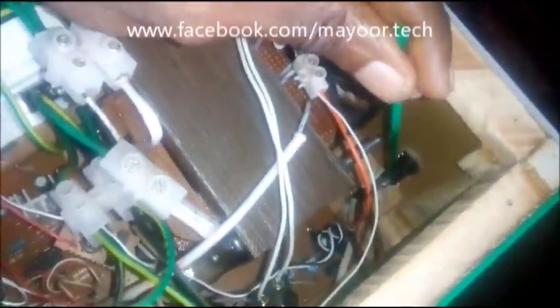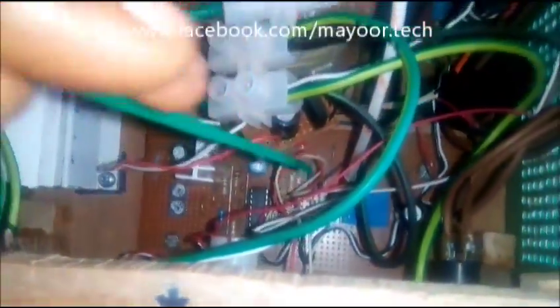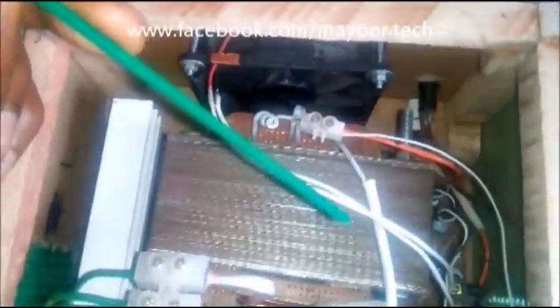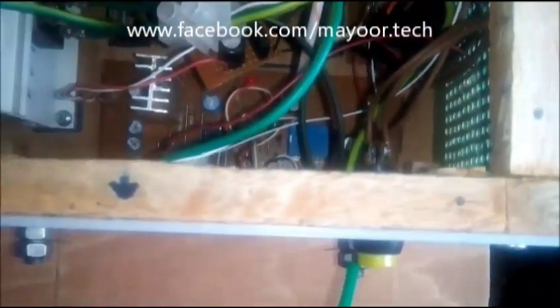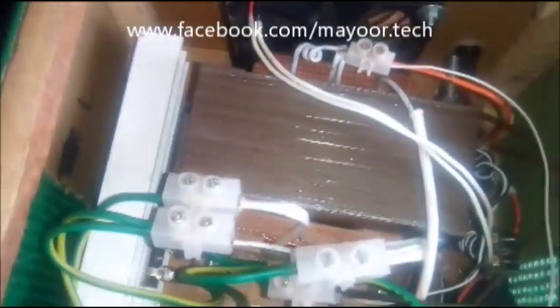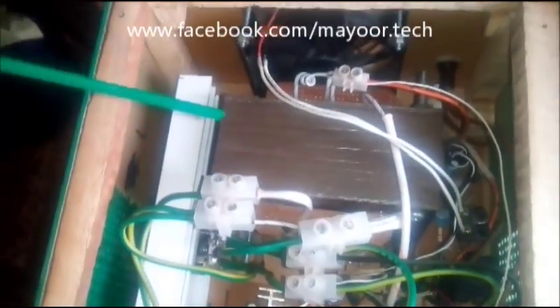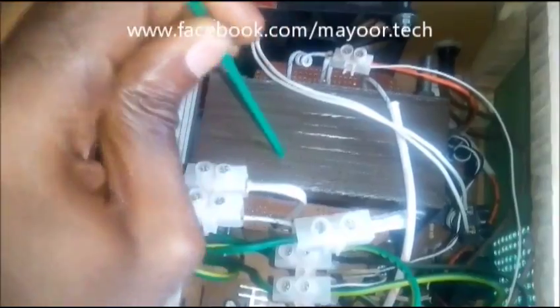It goes into the fuse, comes out from the fuse, goes to my control circuit, comes out from the control circuit, then enters my switch, power switch, before it now gets to the transformer. This configuration enables the control circuit to control when the transformer comes on.